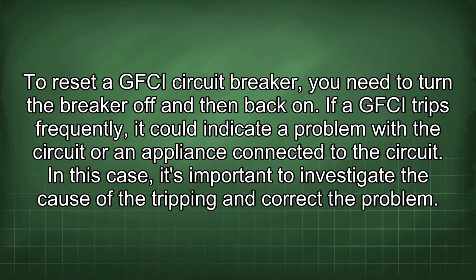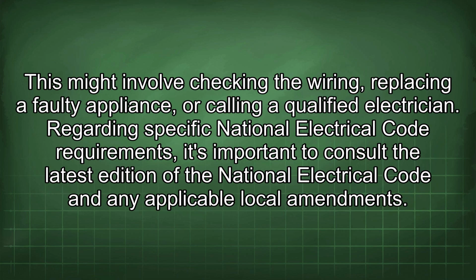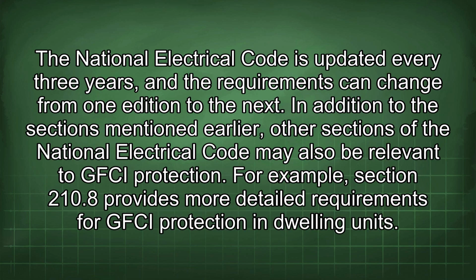If a GFCI trips frequently, it could indicate a problem with the circuit or an appliance connected to the circuit. In this case, it's important to investigate the cause of the tripping and correct the problem. This might involve checking the wiring, replacing a faulty appliance, or calling a qualified electrician. Regarding specific National Electrical Code requirements, it's important to consult the latest edition of the National Electrical Code and any applicable local amendments. The National Electrical Code is updated every 3 years, and the requirements can change from one edition to the next. In addition to the sections mentioned earlier, other sections of the National Electrical Code may also be relevant to GFCI protection. For example, Section 210.8 provides more detailed requirements for GFCI protection in dwelling units.